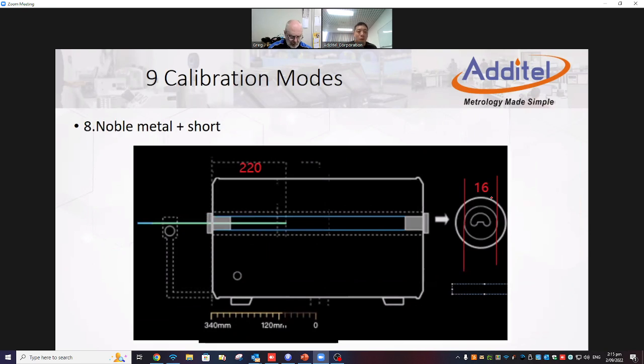One thing I want to say is that we do need to select the calibration mode in the manual, because different modes have different algorithms to optimize the entire temperature. For example, for the short solution, we may concentrate the heating energy on the left side, not the middle or the right side. So we do recommend to select the right mode when they do the testing.